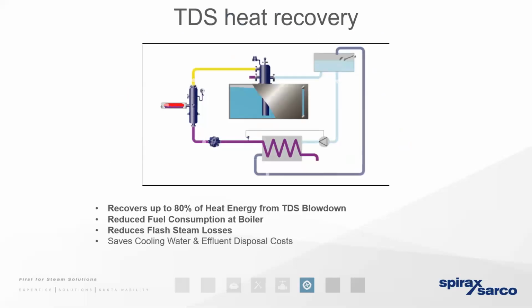But that blowdown still needs to go to waste. It's nasty stuff. We can't use it anywhere else in the process. But as with other areas of site, there's no reason why we can't utilize the flash steam that is produced whenever we get a fall in pressure from the blowdown water, the flash steam, and therefore that total heat energy. It will be clean. It won't have any of the particulate in it, so we can reuse it. And the residual blowdown can go to waste, perhaps being put through a basic heat exchanger where we can use that heat energy to add some temperature to the incoming makeup water, thereby helping us to keep the hot well at a target temperature that's nice and high.